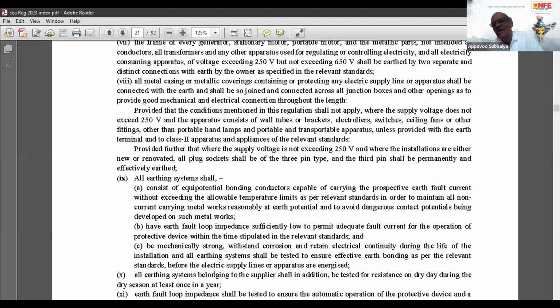Thank you, Mr. Abhijit and Manu, for enlightening this forum. You first ascertain whether your system can meet the earth loop impedance permissible value by conducting a test that includes the supply transformer, PME, and your own system. Then you ascertain whether to connect or adapt a TNS or TT system. In fact, the final objective is to have a TNS system at all consumer premises to have your equipment protected and avoid any overvoltage by providing equipotential bonding. So this is the mantra we have learned from Manu and Abhijit.